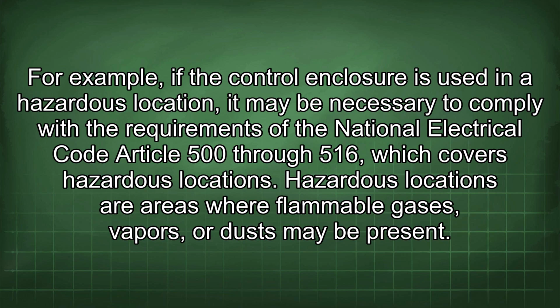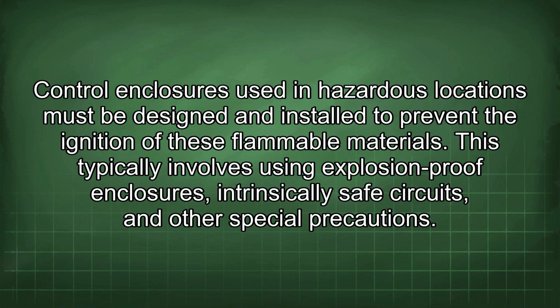For example, if the control enclosure is used in a hazardous location, it may be necessary to comply with the requirements of the National Electrical Code Article 500 through 516, which covers hazardous locations. Hazardous locations are areas where flammable gases, vapors or dust may be present. Control enclosures used in hazardous locations must be designed and installed to prevent the ignition of these flammable materials. This typically involves using explosion-proof enclosures, intrinsically safe circuits, and other special precautions.